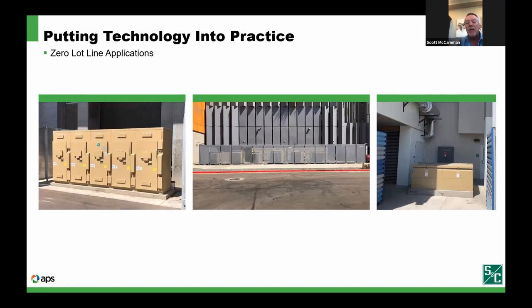and there's adequate space for personnel to get back in there. In addition, we're always looking for head clearance to be able to crane this equipment in. This particular switchgear is actually underneath a 30-foot high, probably third level of the building. So we had to work with them as well to determine if cranes could actually fit in the alleyway and be able to pick this equipment if necessary in the future.